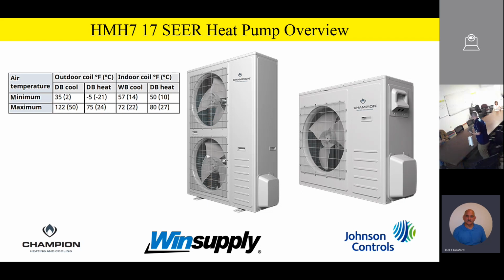As you can see, our minimum temperature for cooling is 35 degrees, and in heating mode it's -5. It should be noted that these products will actually heat at approximately 50% of their capacity all the way down to 0 degrees Fahrenheit outside. That's pretty remarkable for a heat pump. To put that in perspective, a 3-ton heat pump is still making somewhere around 18,000 BTUs of heat at 0 degrees Fahrenheit outside. Our maximum temperature is 122 degrees outside for cooling and 75 degrees for heating. Any questions or comments on that?